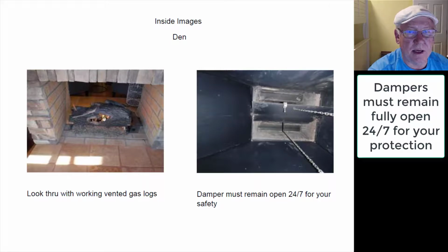And the reason for that is on dampers with vented gas logs, you don't ever want to take a chance where you would close the damper, forget to open it, fire these things up. You wouldn't see or smell the carbon monoxide as it was pouring into the house. So dampers must remain open 24/7, and that's a state code.